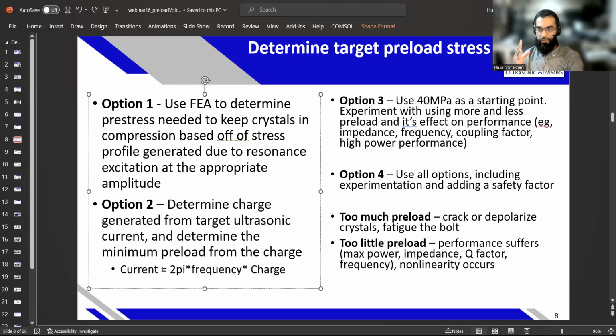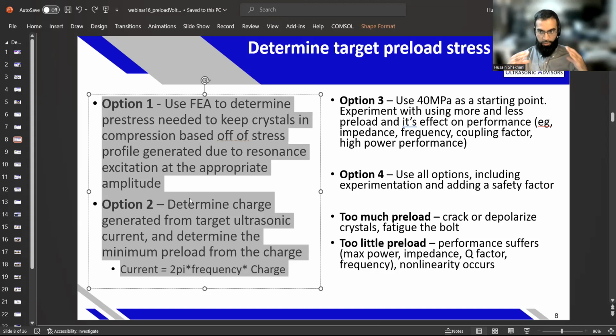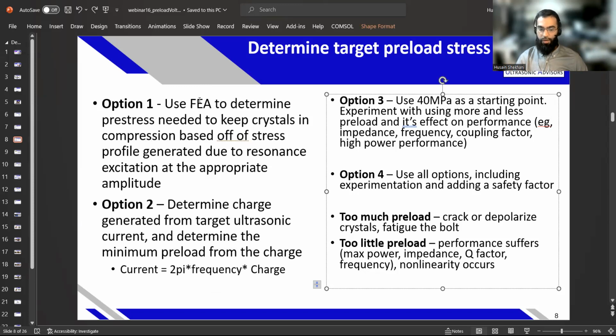Because if you think about it, when the crystals are oscillating in resonance, that current is caused from charge. The charge is coming from alternating displacement or a stress. So the static preload has to counteract all of that excitation to keep it in compression. So these two are mostly talking about putting it into compression, holding it there. It's not specifically addressing the intimate contact, which is purely an experimental thing you need to work through. So these tell you the best case scenario for the stress I'm putting on. And as you get lower in stress, those surfaces will start to separate more and more as you get to a tension state.